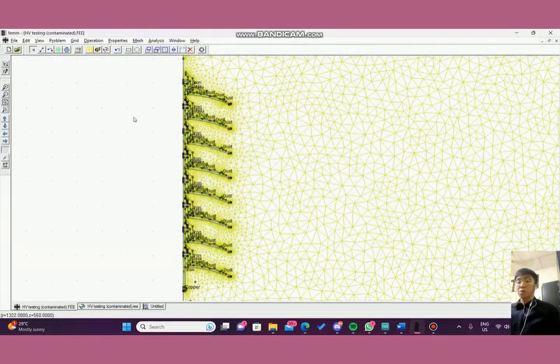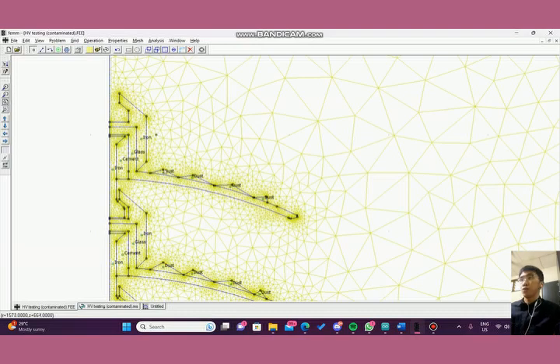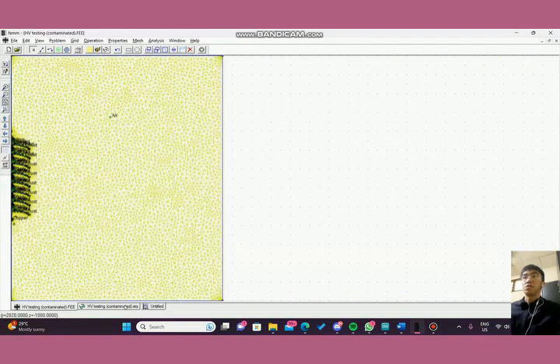So now I'm going to explain the result regarding the contaminant test on the 275 kV glass insulator prototype. This one is the model design of the contaminant test. As we can see, there are irregular shapes here that represent dust accumulated on the surface of the glass disc. So this is the model we modeled, and the next one is the result.